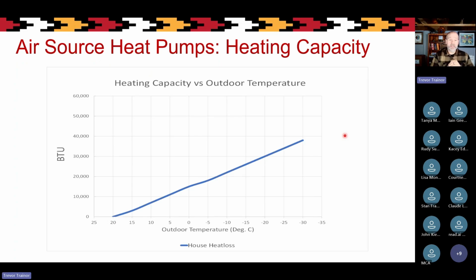The one thing about air source heat pumps, though, is that as the outdoor air temperature gets lower, their capacity starts to decrease. And so when we design a system that's going to be used to heat your home, we have to keep that in mind. This chart shows the heat loss through the walls, roof and foundation of your home at different temperatures. As we get colder from plus 20 to minus 20, the heat loss goes up, and at minus 30, let's say in this example, about 38,000 BTUs. So as the temperature gets colder, heat loss goes up, and we need more heat to maintain our indoor temperatures.